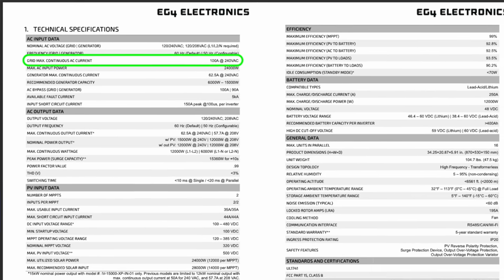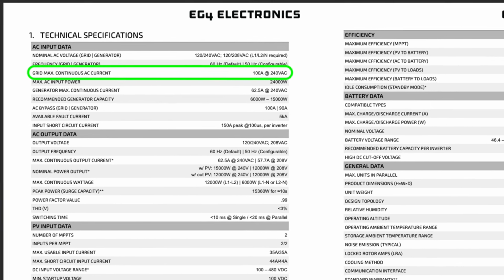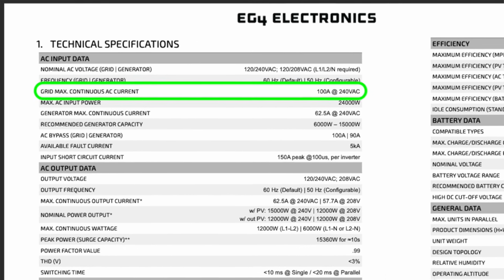So the way this works is it has a grid bypass. You hook up the 12000 XP to the grid, and it can pull up to 100 amps through the inverter and send it to the backup panel. It also has the ability to disconnect from the grid and run off of solar and batteries.